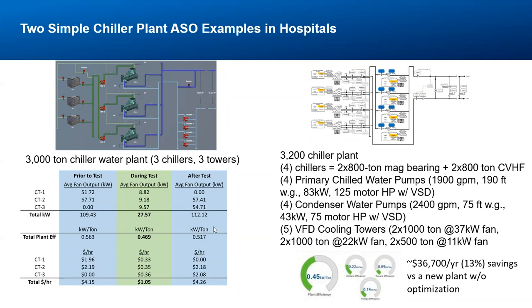This one on the left has been running in automatic mode, commanding the systems for several months. What I'm showing here is findings from a short test, calling out the energy, the average power, the average plant efficiency, and cost per hour of the cooling towers within this plant. You can see prior to the test versus during and after, a significant difference in the amount of fan power energy.